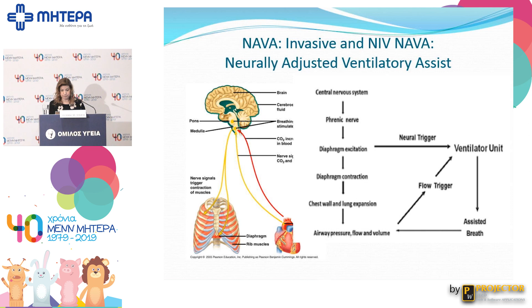But the concept is that the CNS triggers the phrenic nerve, that excites the diaphragm to contract. So in the use of a flow sensor, we're waiting for the diaphragm to contract, the chest wall to move, the lung to expand, and then the air pressure and gas flow to change to sense this assisted breath, whether it's nasal or by endotracheal tube. In this circumstance, there is an NG that is specifically designed by them to have a sensor at the diaphragmatic level to pick up on this diaphragmatic excitation and not wait until the gas flow changes. And in the case of nasal ventilation, like NiPPV, the gas flow may not change measurably enough to trigger that sensor. So the concept is when the diaphragm contracts, the baby's breath is then triggered, even in a non-invasive mode.